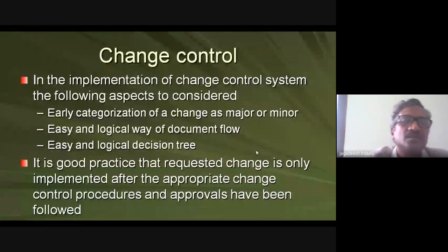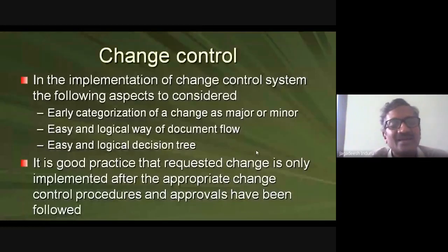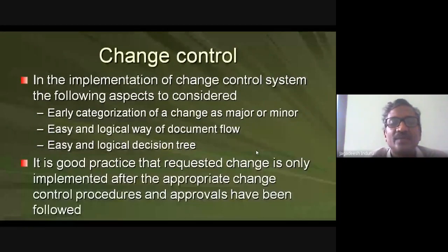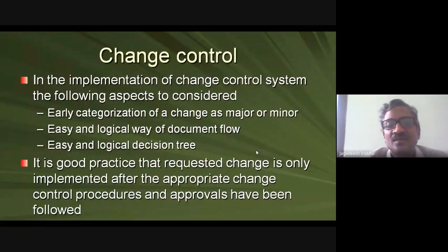If you throw away the old equipment and bring in a new one, validation status is lost and revalidation is required. Change control provides an easy, logical documentation flow with a sequence of dates recording all part changes or major changes, making it easy to decide how often to replace a belt or component. It is good practice that any requested change is implemented only after appropriate change control procedures are followed.